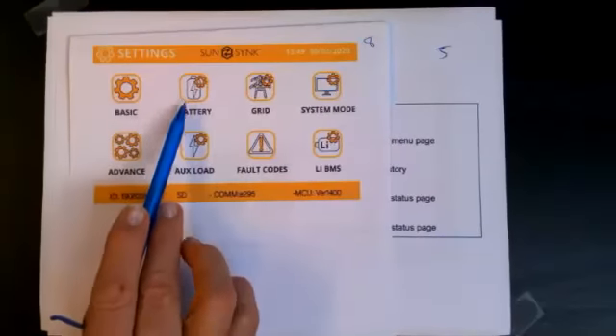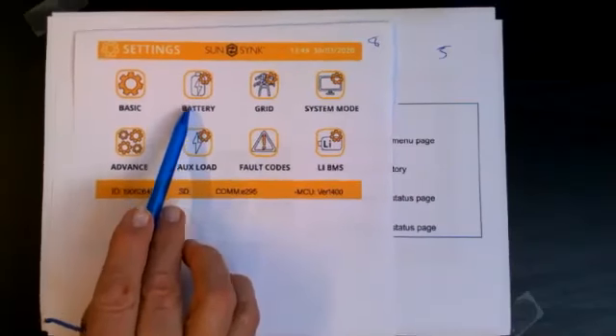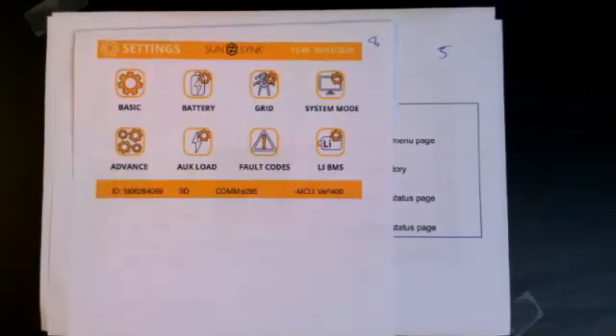Battery, I'll come to the battery in a minute because the battery is very important in the battery settings. Grid. You'll see lots of complicated things on the grid settings. Most of it, ignore. There are certain regulations, for example in Australia, and they have some rules set by the power company, which is absolutely nothing to do with South Africa. And people say, well, what's this? What's this? I'm not even going to go through it because it's fairly complicated. All you need to look at on the grid is your high voltage and your low voltage. This should be fairly tight unless you're at the end of a line, or some people using SWER line.